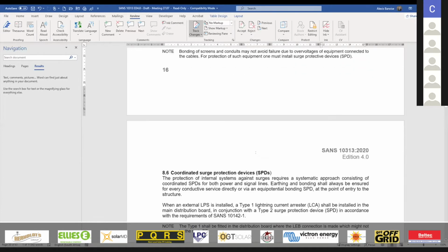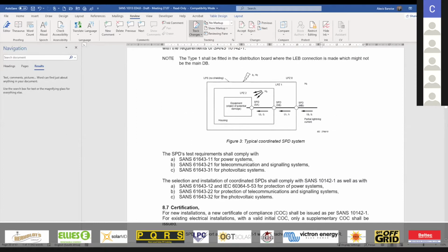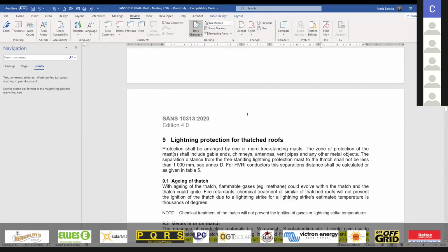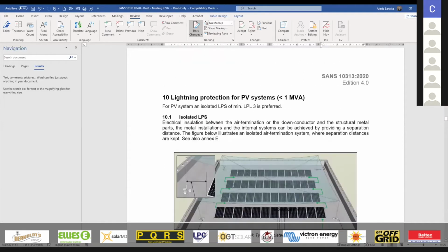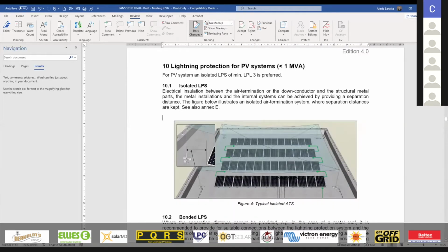Okay, moving on. We want to get to the point where we show you the examples. Here we go. We have in the standard prescribed 2 methods, which we are recommending to people or any EPC, obviously based on the roof itself, which is mostly the driver. So first of all, it's important to note that nothing less than a lightning protection level 3 system will be accepted for PV, and that isolated lightning protection systems are the preferred method. It's not wrong to do bonding. In fact, you sometimes cannot avoid a bonded system, but an isolated one would be the best, because then we are keeping the direct lightning currents away from the entire embedded generator.